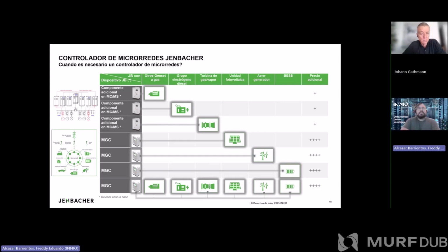This chart helps us understand when a microgrid controller is needed. If we have gas engines, diesel gensets, and turbines, a simple master controller is sufficient. But once we start integrating renewables, which vary so much depending on conditions and must be monitored, it becomes necessary to install a microgrid controller. To this we can add photovoltaics, wind, and batteries. The idea is to have different types of assets and control them optimally to minimize the system's operating costs.